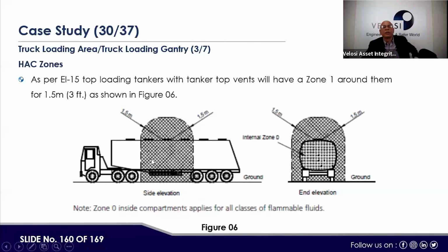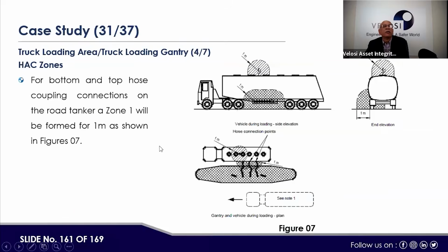So this was as per EI-15. A top loading tanker with a tank top vent will have a zone 1 around it for 1.5 meters, as shown in the picture. In this picture, zone 1 at the area is shown, and there is a zone 0 inside the tanker. This example is used as guidance. Then for the bottom and top hose coupling connection on the road tanker, zone 1 is to be formed for 1 meter as shown in the figure here, where the loading is taking place.